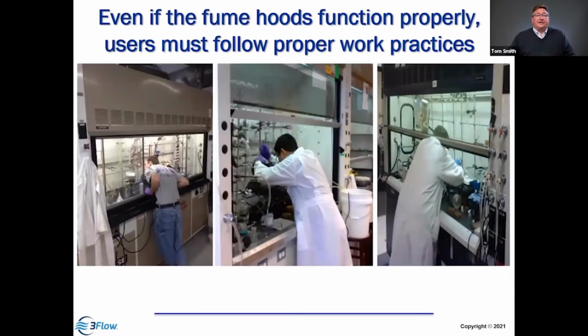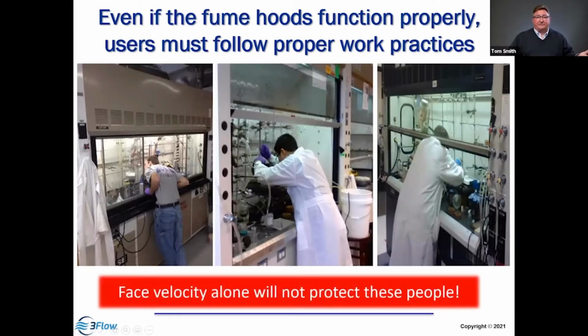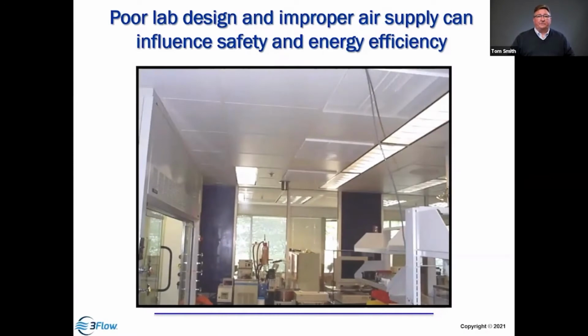All right. And then we look at how the hoods are being used, right? If we have 100 feet per minute and the hood user's putting their head inside the hood, we're not going to be safe, right? No amount of face velocity is going to protect people from exposure if they're working beyond the plane of the sash and exposing themselves directly to the work. It's just not capable of maintaining containment and protecting people under this set of operating conditions. So all of these factors are really important.